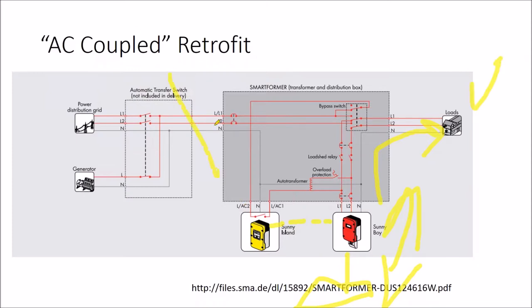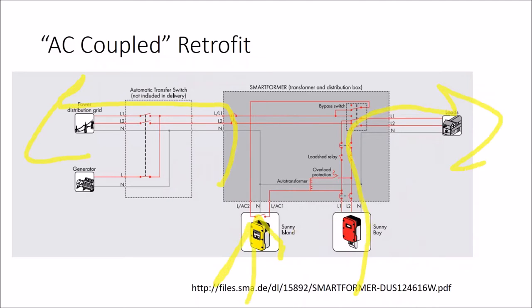That's really only suitable for off-grid, because instead of turning the solar array off and running off the batteries since the batteries are full, you could just keep the solar array on but curtail the power to meet the load. So off-grid, it's good to have everything smart and working together intelligently. But if you're grid connected and your batteries are full, any surplus power from the array is just going to go into the grid. So you don't need to worry about overcharging your batteries or anything like that on an AC coupled system.